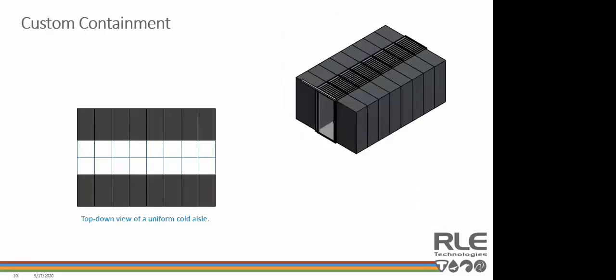When we talk about containment, if you look at the example on this slide, it would be pretty straightforward and easy to contain aisles if they all looked like this. Here, racks are evenly aligned at the ends of the aisle. They're in a perfectly straight row, and all racks are the same height. But really, this is not typical of what we see in most data centers. Over time, plans change, rack heights and rack vendors change. Racks are added or removed to existing aisles, and some unique racks like storage racks don't usually match the height of server racks.